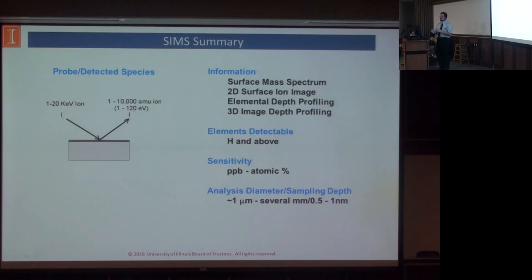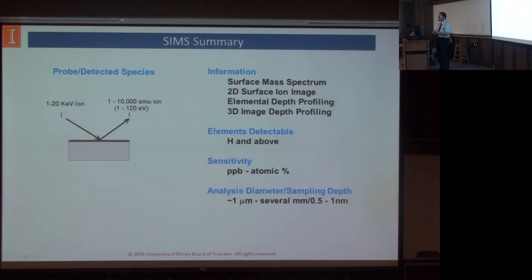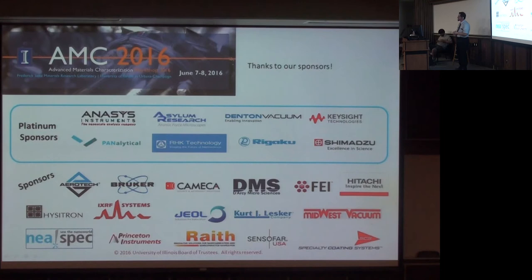To summarize the SIMS technique: we use ions in about 1 to 20 kiloelectron volts coming in and measure the masses coming out — up to 10,000 AMU in specialized circumstances. The types of information we can get include surface mass spectra, 2D surface ion images, elemental depth profiling, and 3D image depth profiling. We can detect all the way down to hydrogen. Our sensitivity can be from parts per billion up to atomic percent. Sampling depth tends to be in the nanometer range.